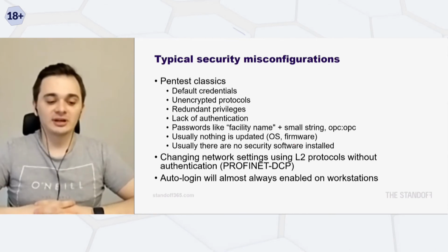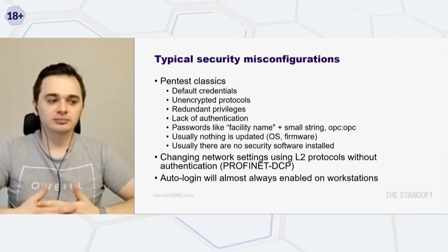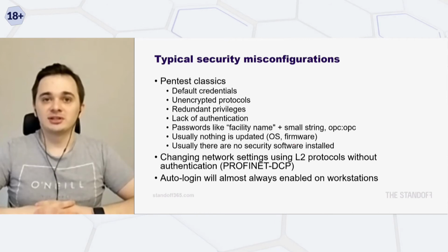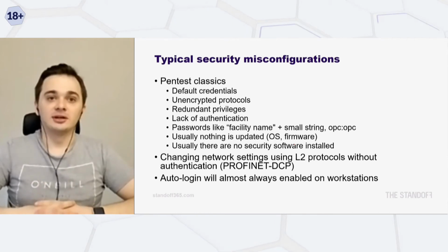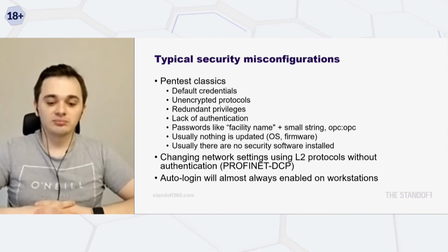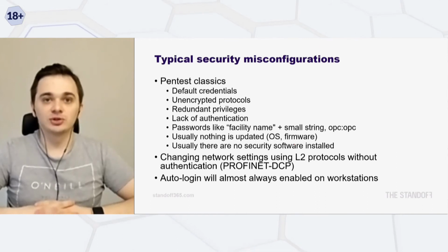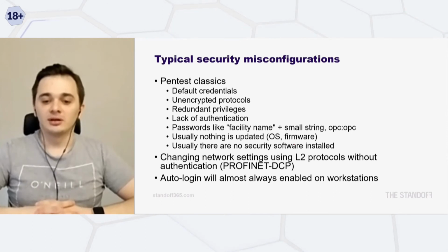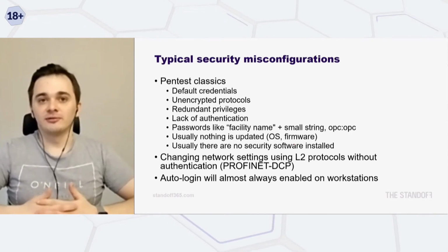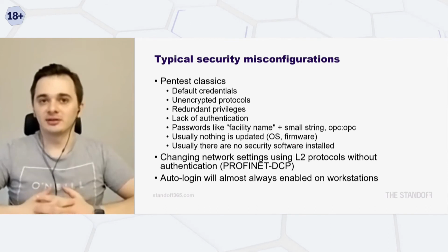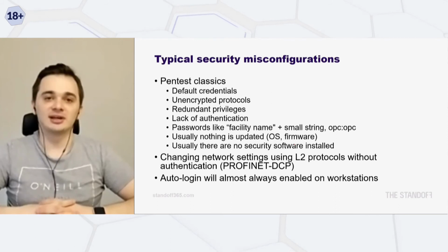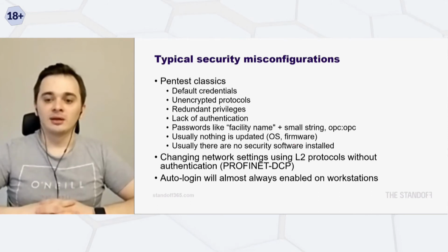Often, the firmware is not updated. Installing updates means that your process must not be interrupted by those updates. And it means that your process must be very resilient. Often, updates are not possible during operational time, and the firmware is updated during the maintenance window when your facility stops once a year for maintenance of the main equipment.